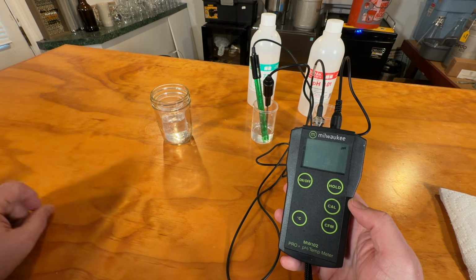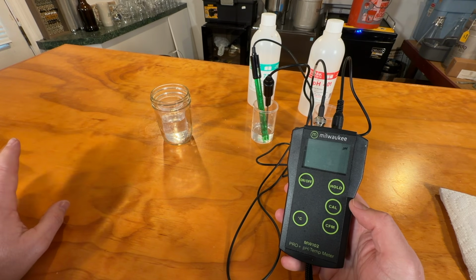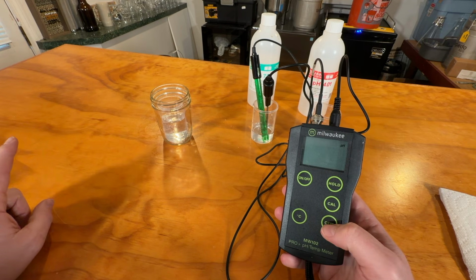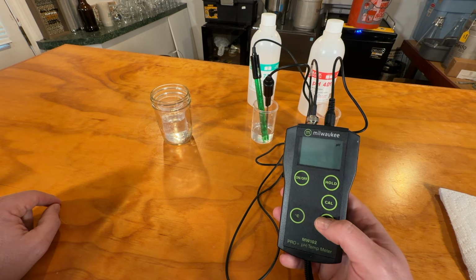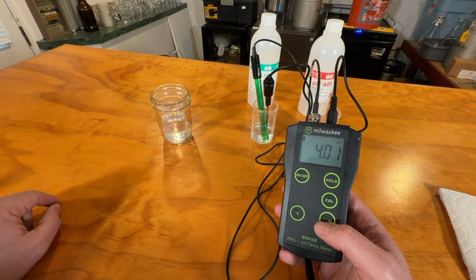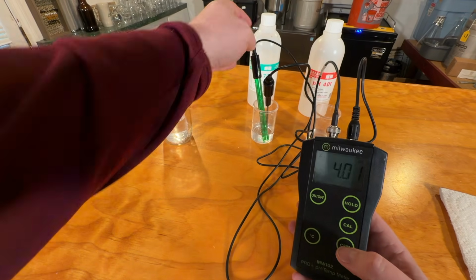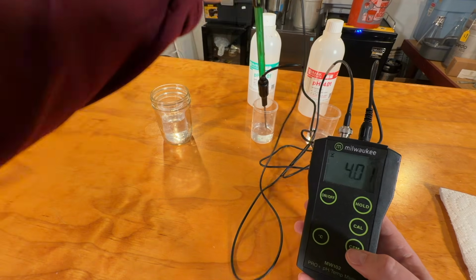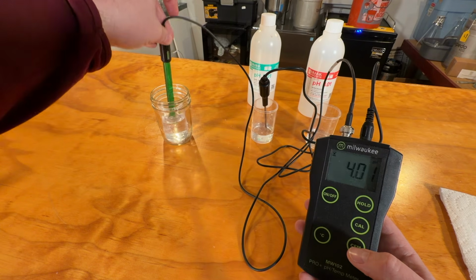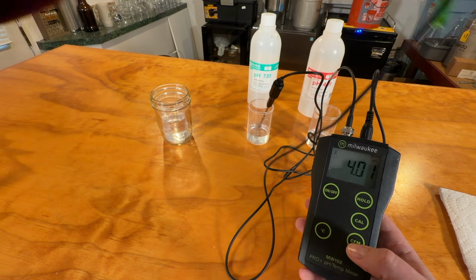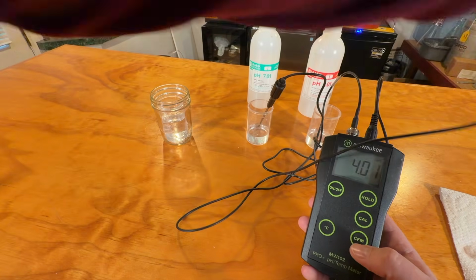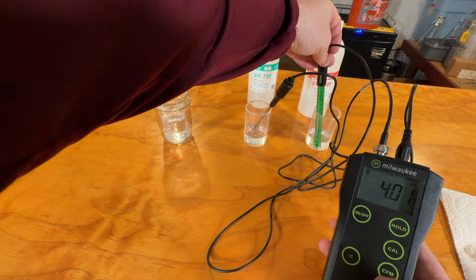So what it's telling you is that I have now calibrated to 7.01. You need to tell the meter that you like that reading. You say confirm. That's what this button is, confirm. And when you hit confirm, it'll automatically start calling for the 4.0 solution. So I'm going to do this. I'm going to give it a little rinse, dab without spilling, right? So put that in the 4.